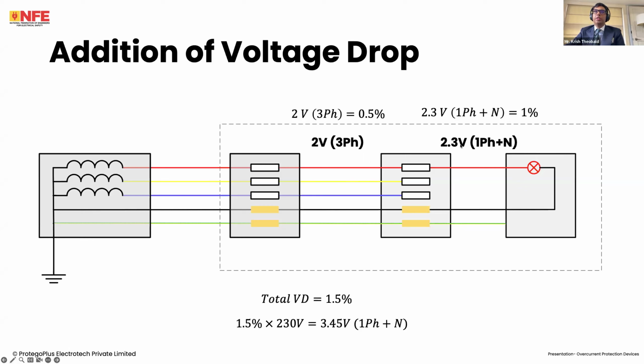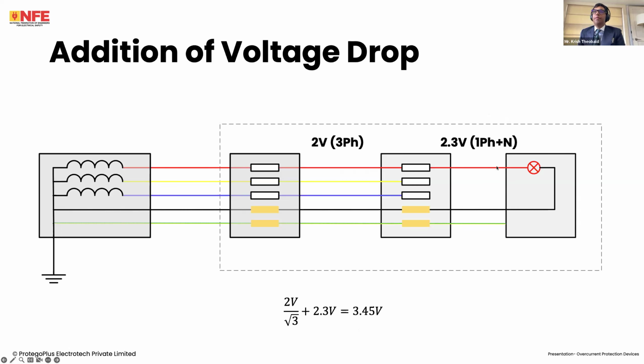So there are two things. First thing I can consider is percentage voltage drop. 2 volts out of a 400-volt three-phase circuit is 0.5%. 2.3 volts out of 230 volts for one phase versus neutral is 1%. So 0.5% plus 1% is 1.5%. So total voltage drop is 1.5%. Utilization voltage is 230 volt nominal. So 1.5% of 230 volt gives a total volt drop of 3.45 volts here. Other approach: take the three-phase volt drop, divide by root 3 and add it to the single phase plus neutral volt drop. Same value we get.